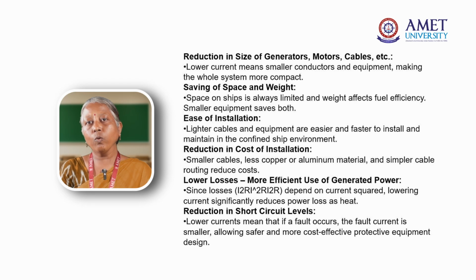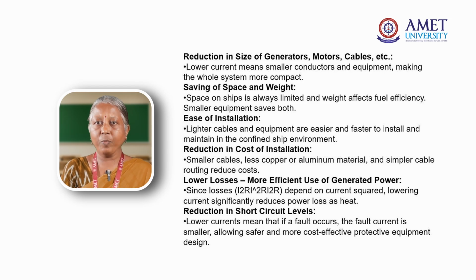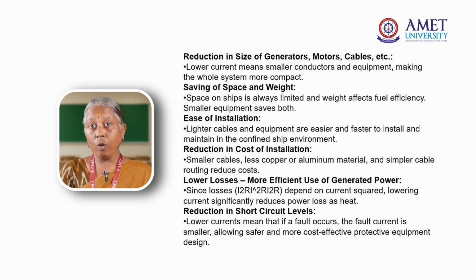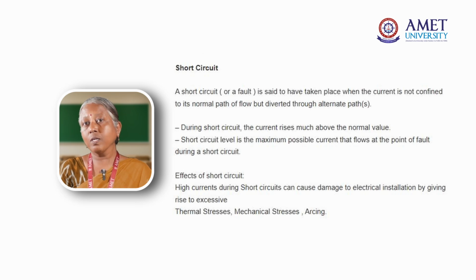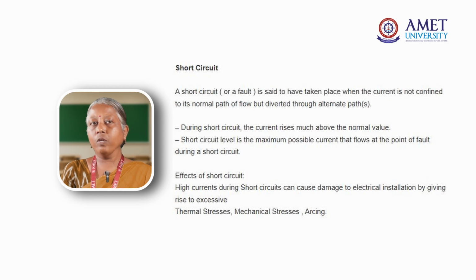So when you go for reduced current, the space required for the generator is less, the size of the generator is less, and the weight of the generator is less. So the space occupied by the generator is reduced. Then ease of installation: since the size and weight are less, the installation is very easy. Then cost reduction is also possible. Then reduction in short circuit level. Since the current is less, the short circuit level onboard goes down when there is any fault. When a failure occurs, you can easily rectify the problem.